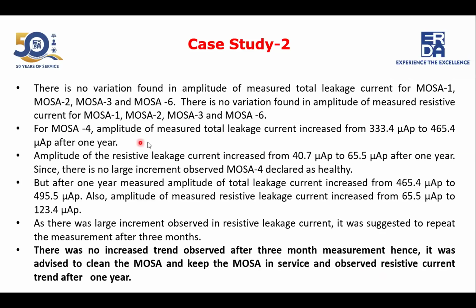But for MOSA 4, the amplitude of measured total leakage current increased from 333 to 465, and the resistive leakage current increased from 40 microampere to 65 microampere. After 1 year it again showed an increasing trend, so we asked them to measure again, and there was no increasing trend after 3 months. Hence it was advised to clean the MOSA, keep it in service, and observe the resistive current trend after 1 year.